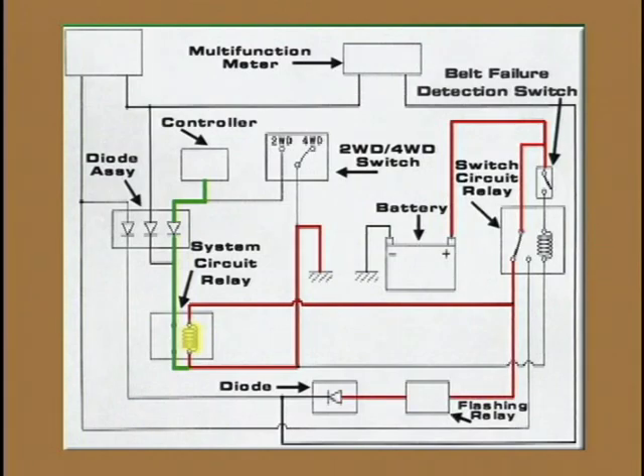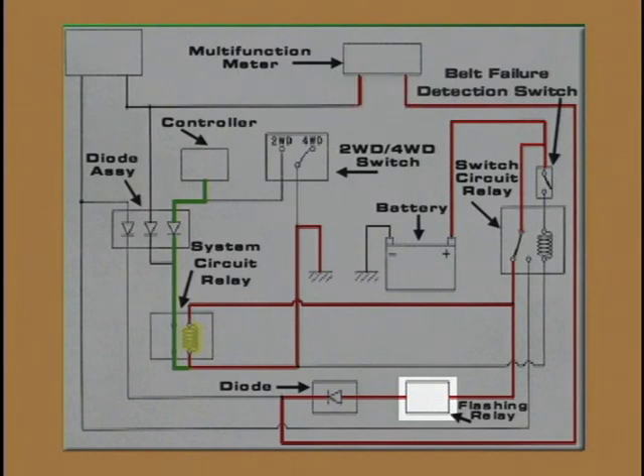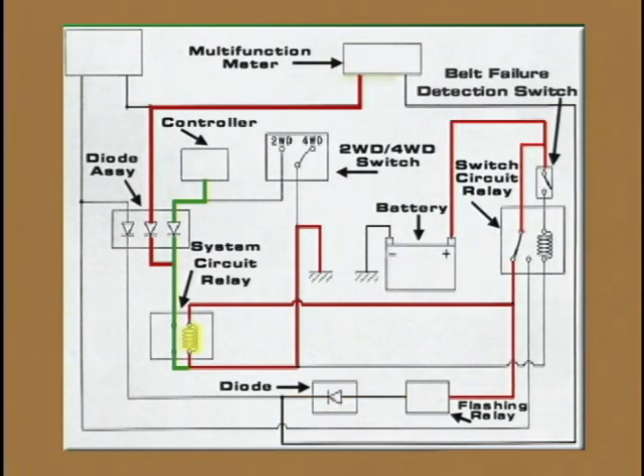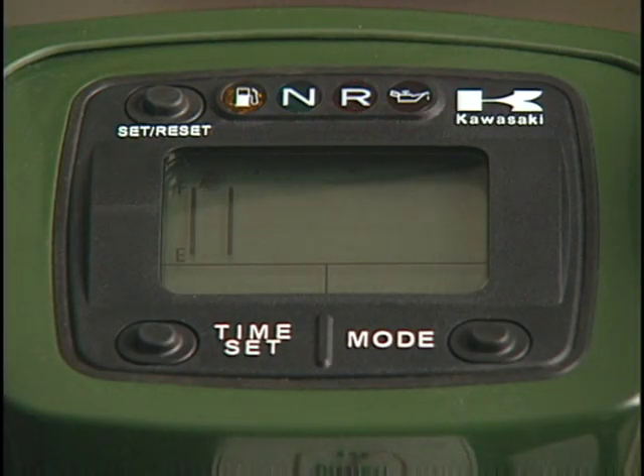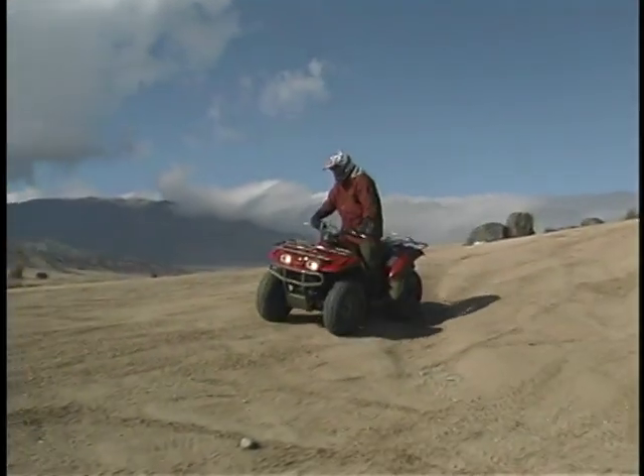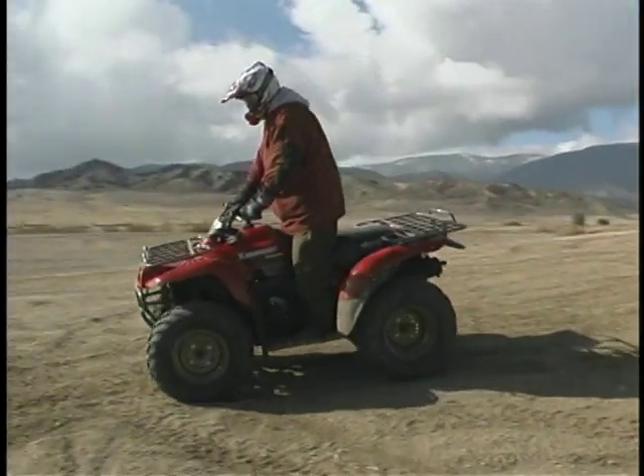When the warning display circuit is activated, voltage is supplied to the flashing relay from the switch circuit relay through the diode and then to the multifunction meter. During activation, the flashing relay opens and closes, causing the voltage supply to the multifunction meter to cycle. This causes the multifunction meter to flash a failure indication pattern. Finally, the controller recognizes the problem and limits the engine to 3,600 RPM.